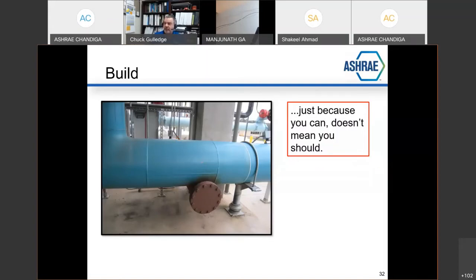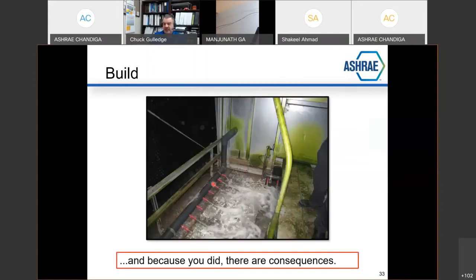This location happens to be after the fourth of four cells. So the water volume is the biggest, the flow rate is the largest. And when they put that sand filter in and changed the dynamics, because they did, here are the consequences. All of the nozzles they put in sucking all the water out at a much higher velocity at the point they did, they sucked the towers dry. They dumped all of the chemical dispersion that was taking place inside the loop of the condenser water. They were getting air into the collection. They were cavitating the pumps because there was truly now air inside the system. All of this was exposed and the residency time of the chemical treatment was gone. And look at all the green stuff growing inside the cooling tower.